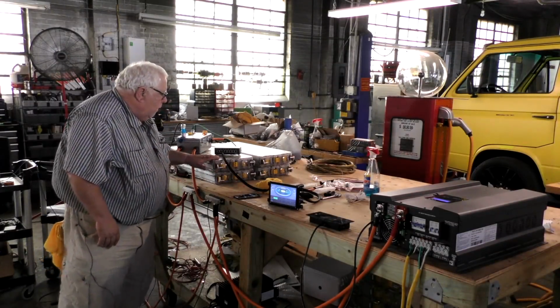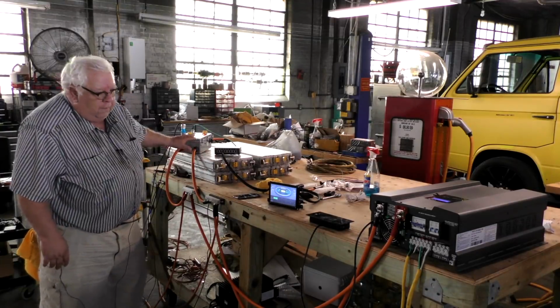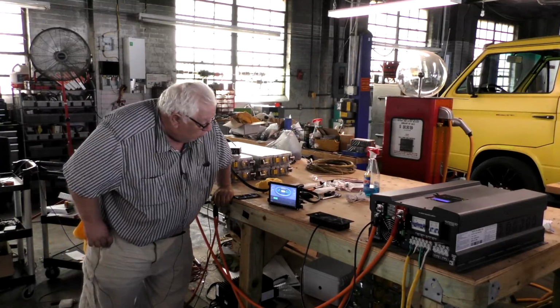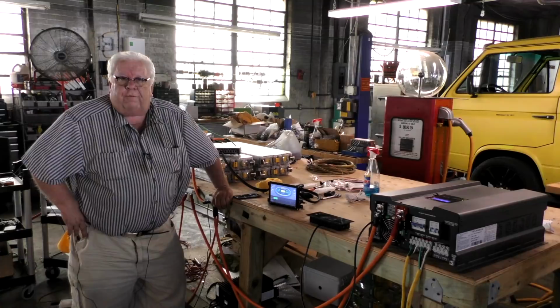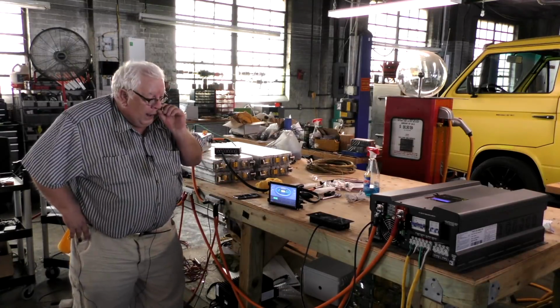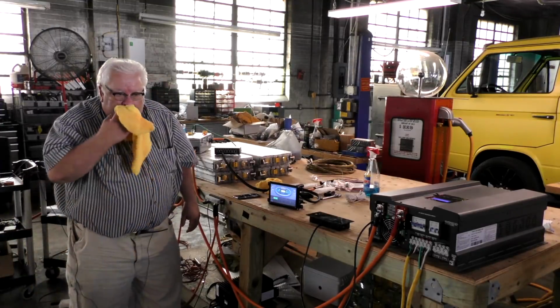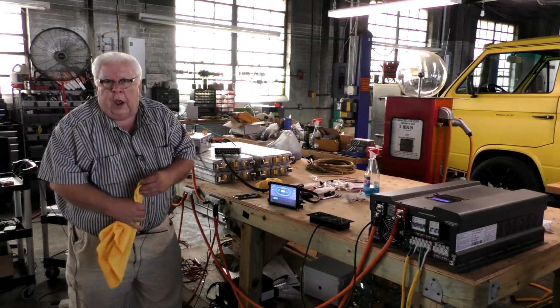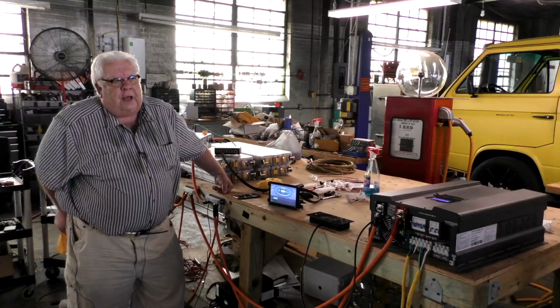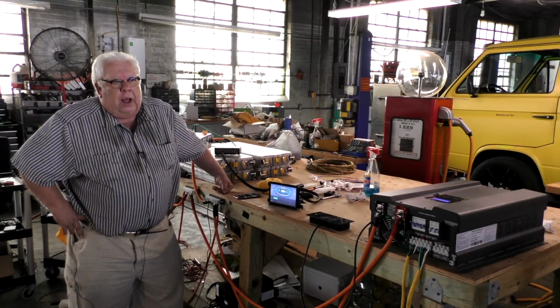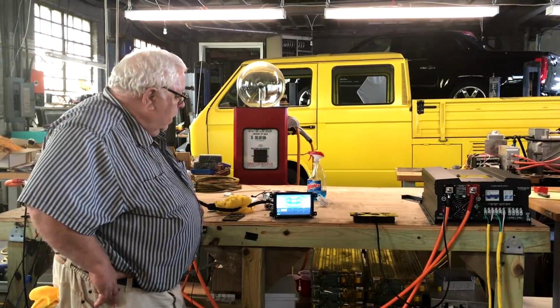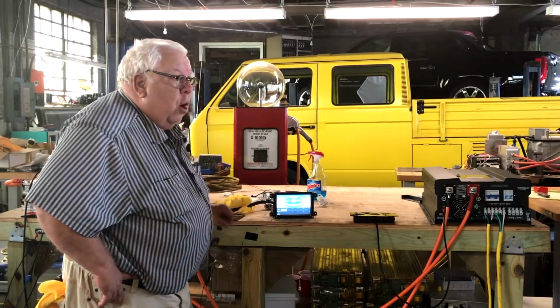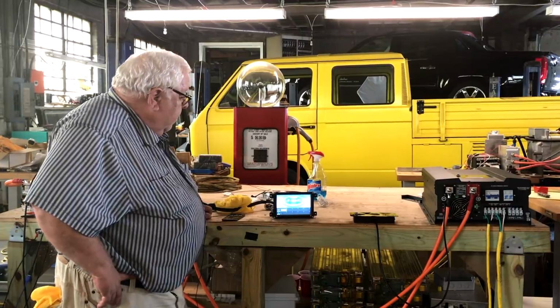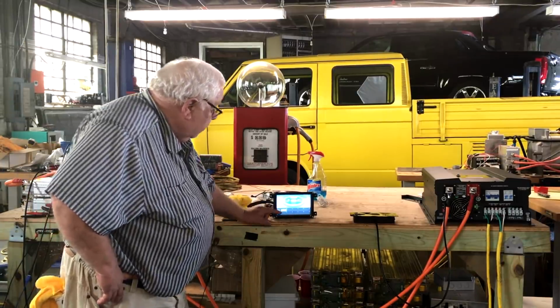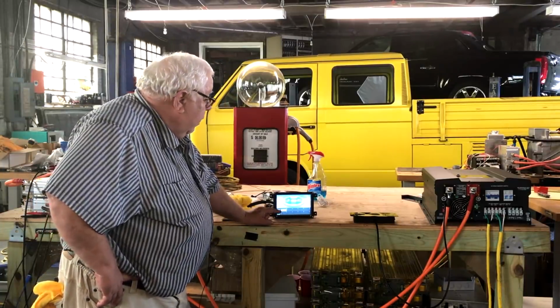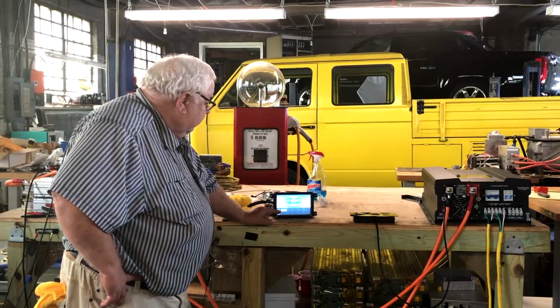Okay, so here we are. We're using our 20 kilowatt 48 volt battery and our battery controller, and this is our EVTV display. We're showing 43 volts at 96 amps, a little over 4,100 watts, and we're waiting for our timeout on the Solar Edge number 1, a 5 kilowatt inverter. With today's sun, 4 o'clock, kind of sunny out, I'd say we got a shot at 2,500 or 3,000 watts. So this should cause our current to go down right smart when this kicks in here in about 15-20 seconds. We should see this 96 amp discharge from our battery drop fairly precipitously when that kicks in.